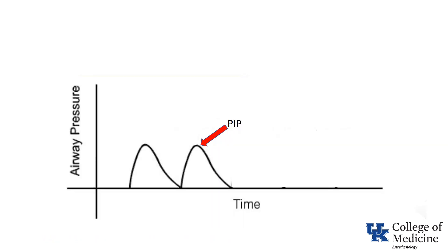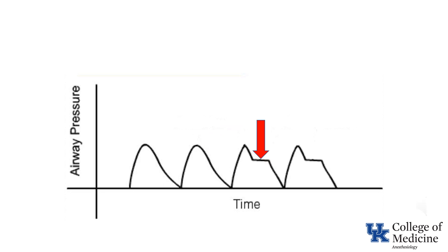This is a graph of airway pressure over time. With standard volume-limited or pressure-limited ventilation, the ventilator achieves its volume or pressure limits and then immediately cycles to the expiratory phase. The maximum pressure achieved — the peak inspiratory pressure — occurs immediately prior to cycling to exhalation. As you can see from the last two waveforms, an inspiratory pause, also known as an inflation hold, has been added at the end of inspiration.